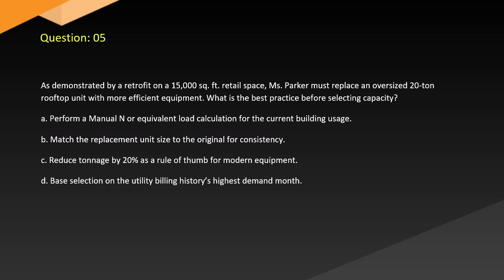A. Perform a Manual N or equivalent load calculation for the current building usage. B. Match the replacement unit size to the original for consistency. C. Reduce tonnage by 20% as a rule of thumb for modern equipment. D. Base selection on the utility billing history's highest demand month.